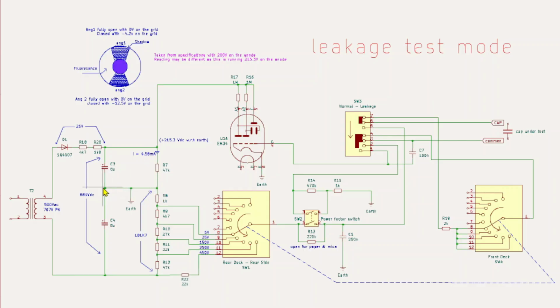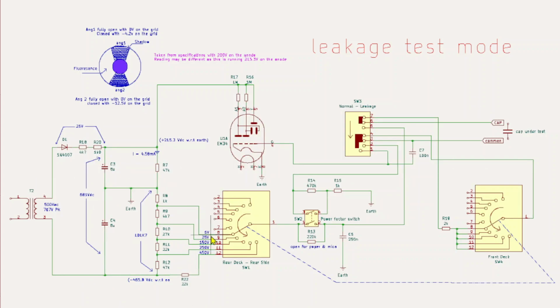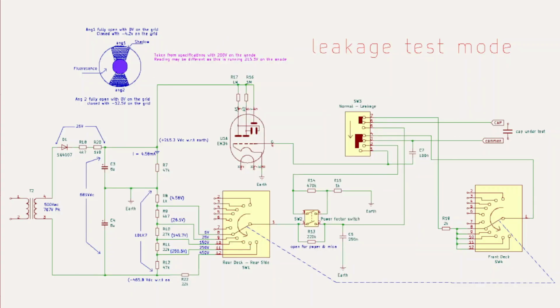This is a strange circuit because it references earth to the center of a divider chain, and so we know that the voltage on this side, if you've worked out the current down there as well with Ohm's law, is going to come out as minus 465.8. So a bit bigger than the 415 they claim on there. And if we keep on looking at it, they say that that's a 5 volt tap off. And so if we measure 4.58 milliamps flowing through 1k, the voltage across it is going to be 4.58. So 4.5, 4.6 volts should be 5. And if we go along working it up, we'll find that each time we look at the taps with the current flowing, we are getting close to the voltages that they state in the book. So that's the first part.